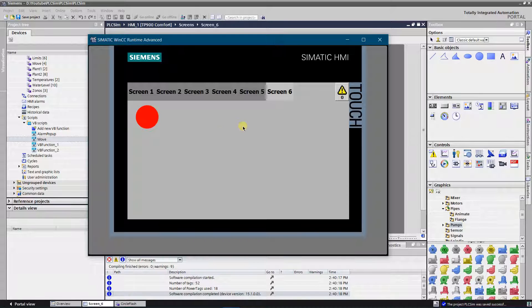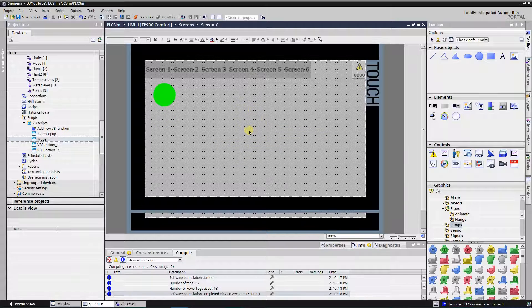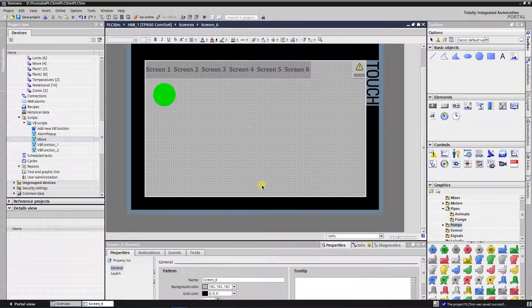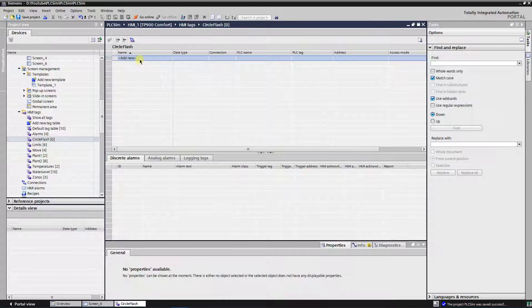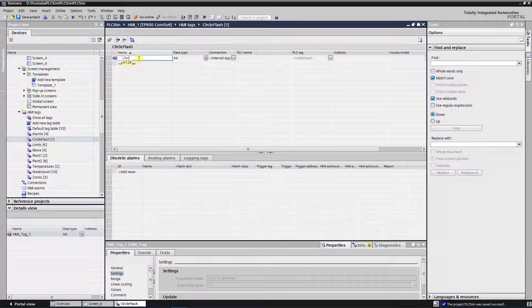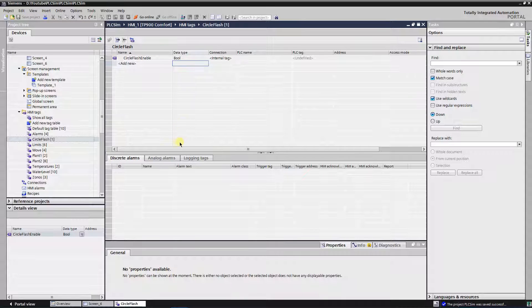That is how the standard flashing property works. It is uncontrollable — it starts immediately after the corresponding screen is activated. To add some control to the flashing, an animation called visibility needs to be used. This animation is used with a tag connection, meaning that object visibility is changed at runtime depending on the value of the connected tag. Let's create a tag of type bool that will be connected to the visibility property. To invert the state of the tag I will use a button.